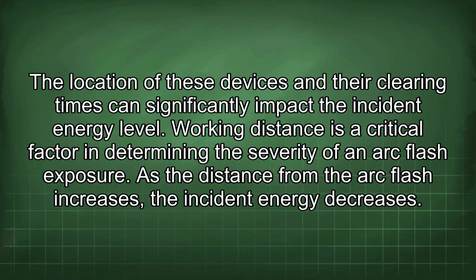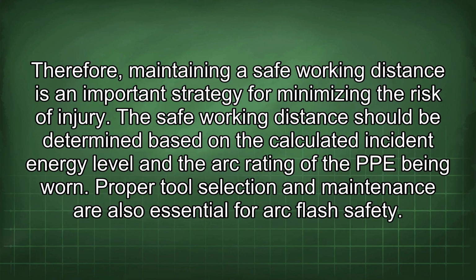Working distance is a critical factor in determining the severity of an arc flash exposure. As the distance from the arc flash increases, the incident energy decreases. Therefore, maintaining a safe working distance is an important strategy for minimizing the risk of injury. The safe working distance should be determined based on the calculated incident energy level and the arc rating of the PPE being worn. Proper tool selection and maintenance are also essential for arc flash safety.